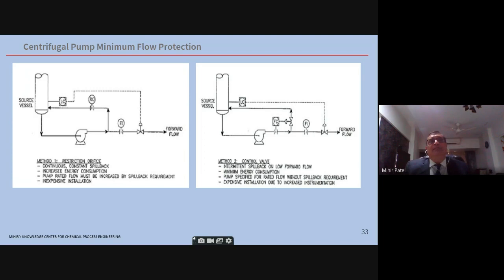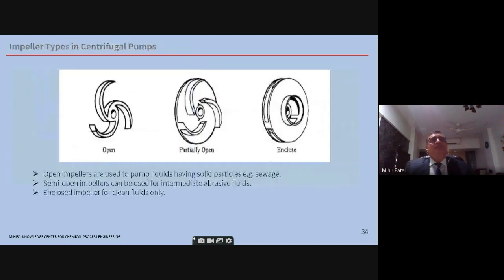So that means the pump now has to be ordered for 5 meter cube only. So that's a fundamental difference between these two types. The impeller types. Here you can have open, partially open, enclosed. As I've written down, open impellers are used for services with solid particles. Let's say sewage is there. Semi-open impellers can be used for intermediate abrasive fluids. And enclosed impellers normally occupy a majority of the services. 80-85% are enclosed type. They give better efficiencies and they are for clean services only.